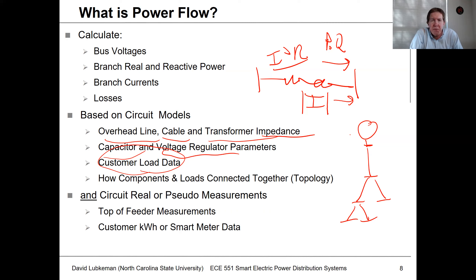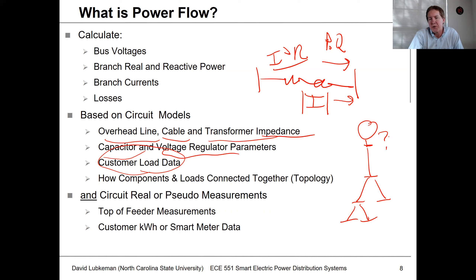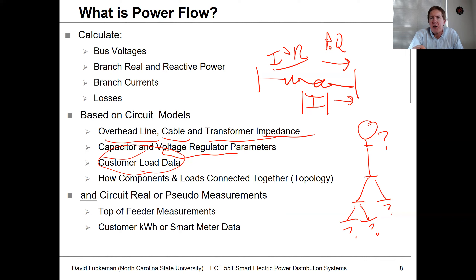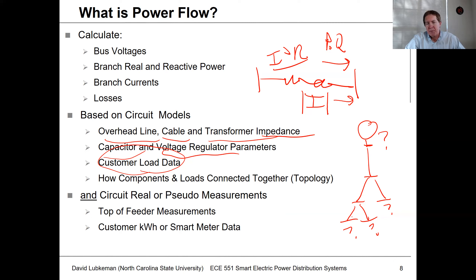Once we have all this information, the final piece is measurements. We need to know the top-of-feeder measurements, which we can get through a relay. We need some information about the loads, from various data sources such as kilowatt-hour billing information, transformer KVA sizes, or smart meter data for customer locations. Depending on what we have, we go through different types of data manipulation to come up with the load model.